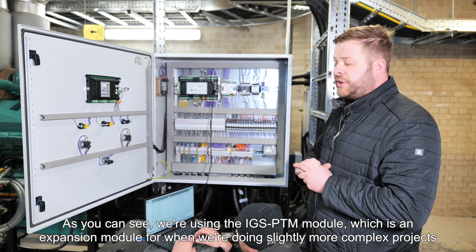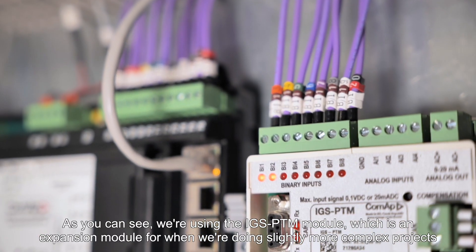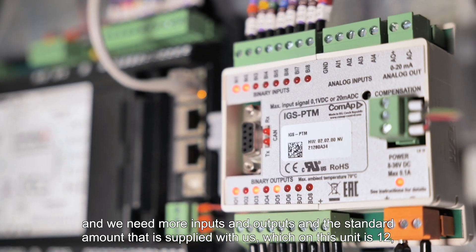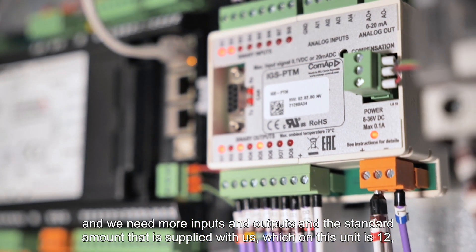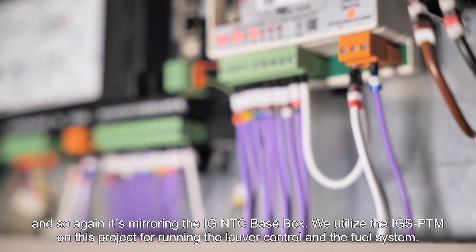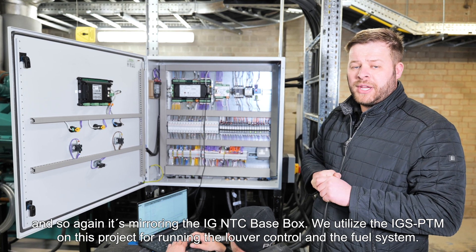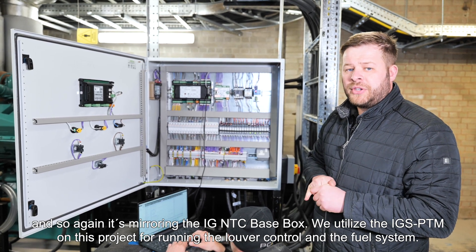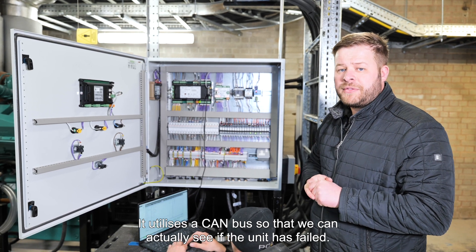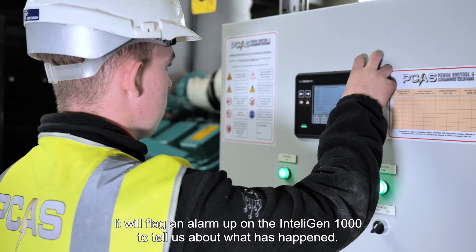As you can see, we're using the IGS PTM module, which is an expansion module for when we're doing slightly more complex projects and need more inputs and outputs than the standard amount supplied, which on this unit is 12. It's mirroring the IGS NTC base box. We utilise the IGS PTM on this project for running the louver control and the fuel system. It utilises a CAN bus so that if the unit has failed, it will flag an alarm on the InteliGen 1000 to tell us that has happened.